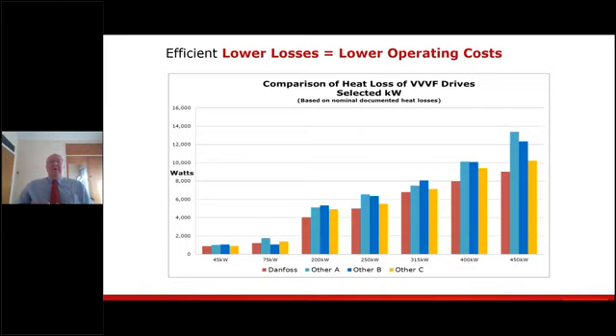However, all manufacturers state the typical power loss from their variable speed drives and the associated optional filters for each kilowatt size, because this enables the correct sizing and selection of any air conditioning system which is servicing the switch room that the VSD is installed in. So a comparison of the typical power loss from the Danfoss drive with that from drives from other manufacturers, including optional filters required to give the same performance, typically results in lower losses and lower heat load on the switch room air conditioning from the Danfoss drive. This results in lower operating costs and can result in lower switch room costs for a project if fewer or smaller air conditioning systems are required for the switch rooms.